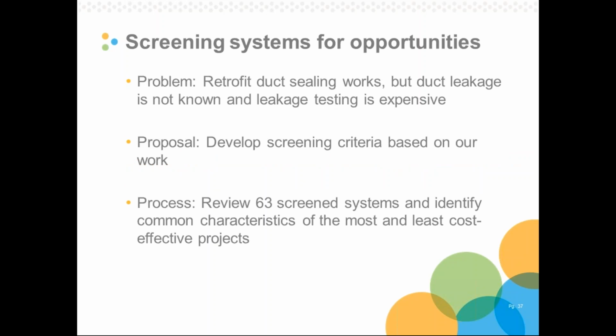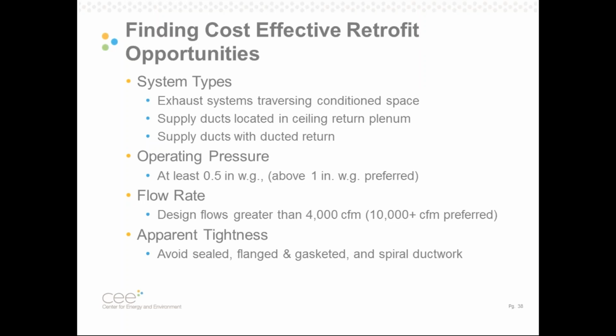So we have this fundamental problem. Retrofit duct sealing works really, really well, but leakage is not known beforehand, and testing is expensive. So what do we do with that? Well, we proposed that we would study everything that we did and develop some screening criteria we could use to find the good opportunities and separate them from the cost-ineffective opportunities. So we reviewed about 63 systems, identified all the characteristics we recorded about them, and came up with some criteria that we hope we could use to rule out the bad systems and find the good ones. We ended up with 4 criteria. We landed on system type, operating pressure, flow rate, and apparent tightness.